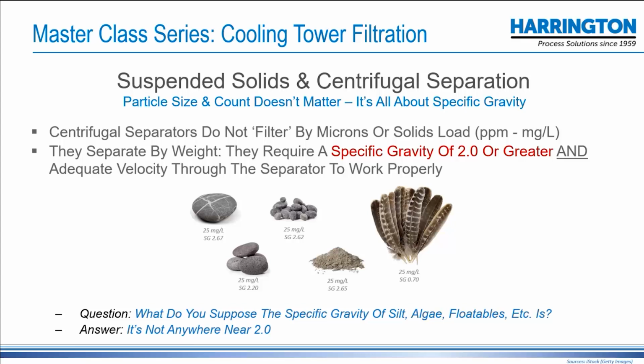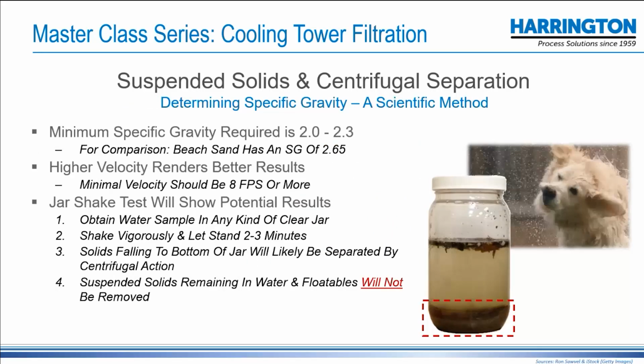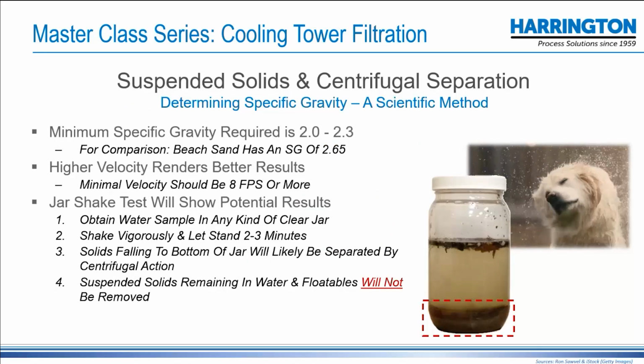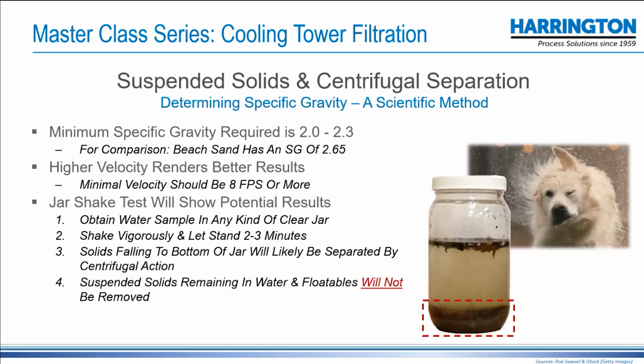It's less than 2.2. And so a centrifugal separator is not going to draw that out. The only thing a centrifugal separator is going to do for you is high weight solids like sand or grit. It'll do nothing with the entrained solids. There's a very scientific method for finding out what a centrifugal separator will do for you.